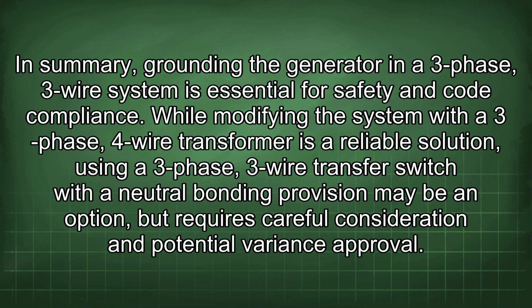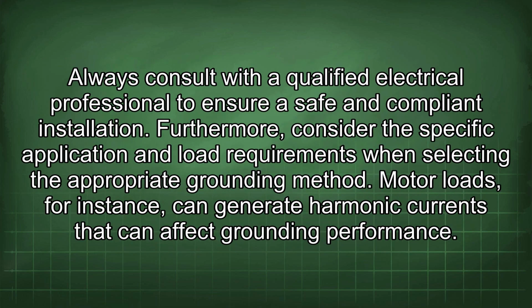In summary, grounding the generator in the three-phase, three-wire system is essential for safety and code compliance. While modifying this system with a three-phase, four-wire transformer is a reliable solution, using a three-phase, three-wire transfer switch with a neutral bonding provision may be an option, but requires careful consideration and potential variance approval. Always consult with a qualified electrical professional to ensure a safe and compliant installation.